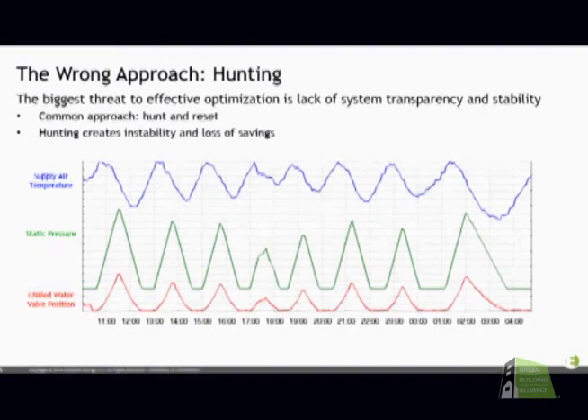Now, to compensate for that, the static pressure is going to jump up. So what's happening within the air handling unit, you have the VFD speeding up, fan speed increasing, you're using more energy, and simultaneously, when that happens, the chill water valve is going to open up because now the chill water temperature is going to sense that they're using a little bit more. So in order to compensate for that, you're going to have both of these things happening in concert with one another. The static pressure is going up, fan speed's increasing, chill water valve is opening up, and so you sort of overcorrect. And the system recognizes this, so now you try and choke back down.